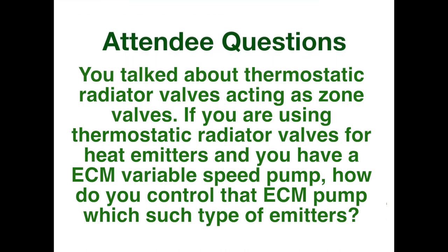I think we have one more question and then maybe give it a wrap. Okay. The question is, you've talked about thermostatic radiator valves acting as zone valves. If you are using thermostatic radiator valves for your heat emitters and you have an ECM variable speed pump, how do you control that ECM pump with such type emitters?